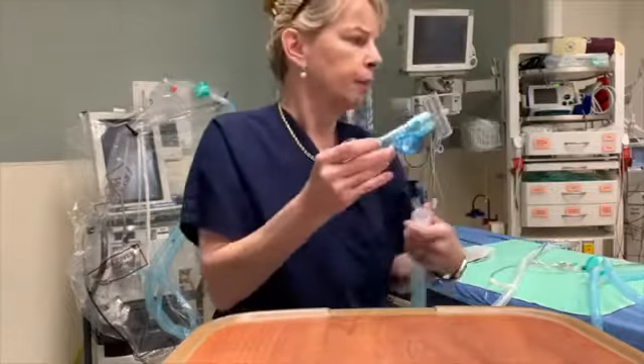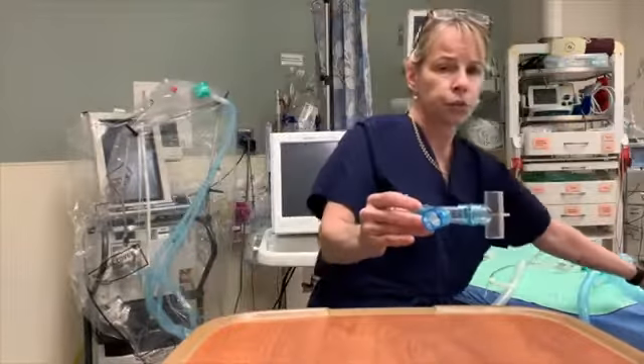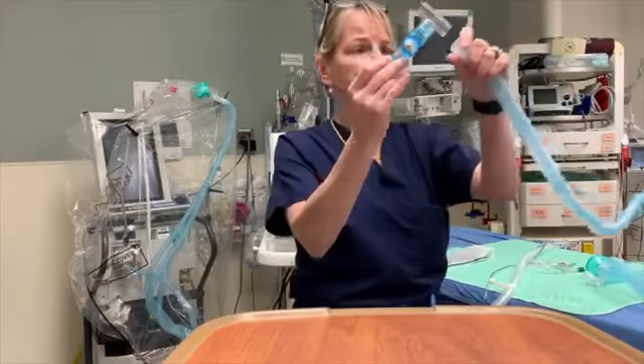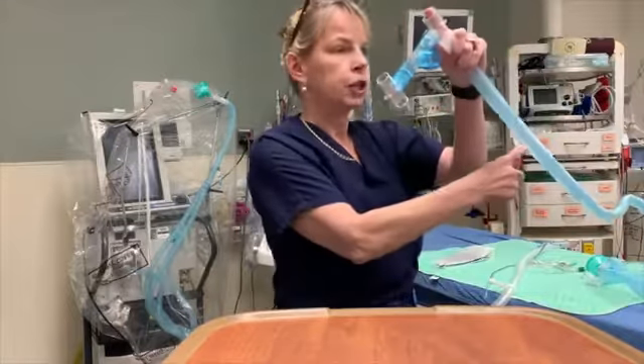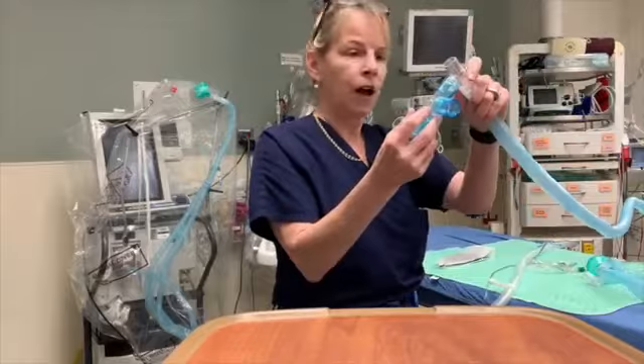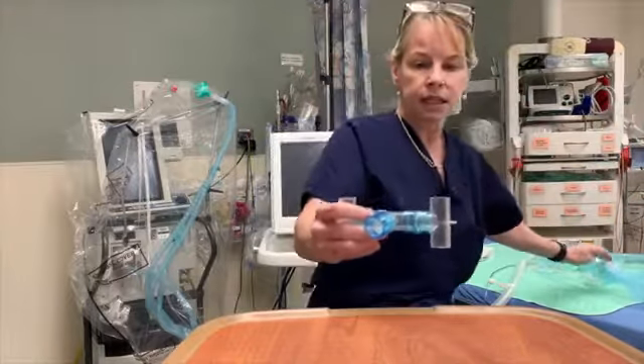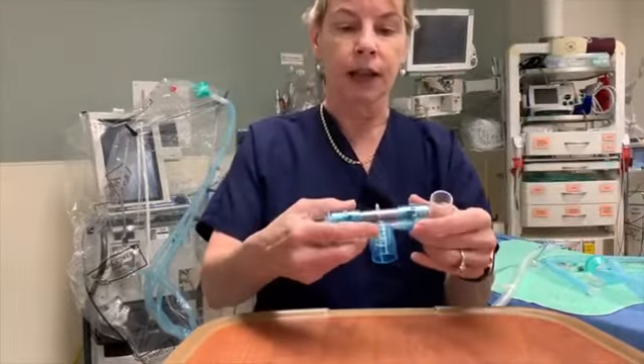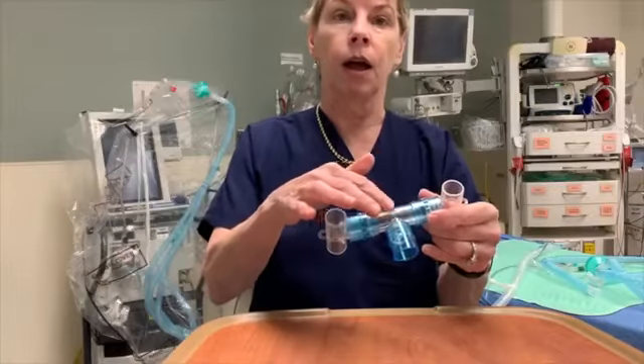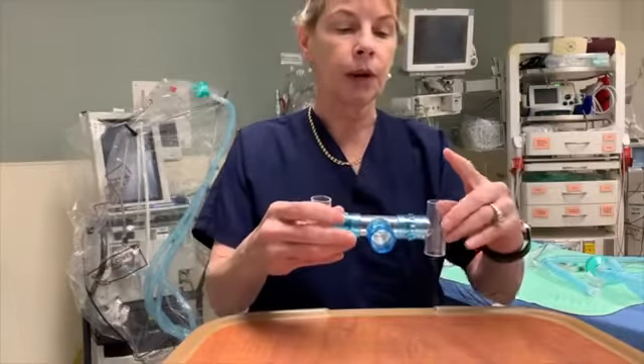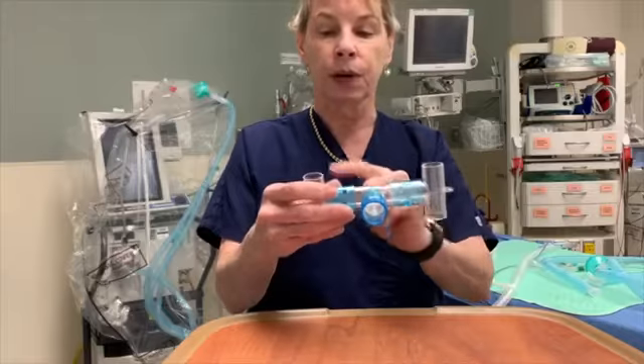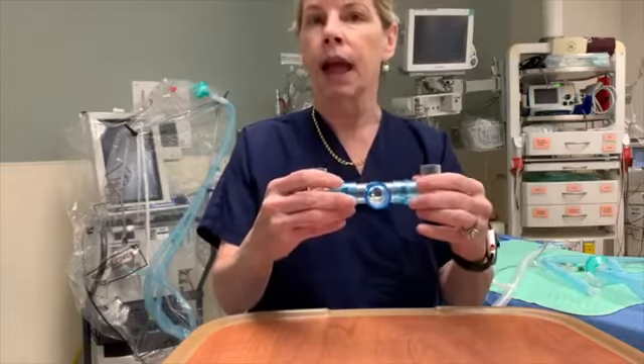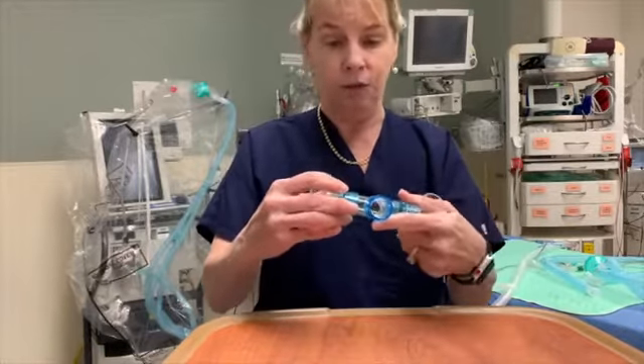Now, there was some question about the cross-contamination infection risk, which is real. And remember, this is coming from the ET tube of the patient, if this is the expiration port, and that's about 5 feet of tubing. But when it gets to this point, right before it goes into the ventilator, is the area where the gases can mix. So if you put a filter before the expiration port, that might mitigate that cross-contamination infection risk.